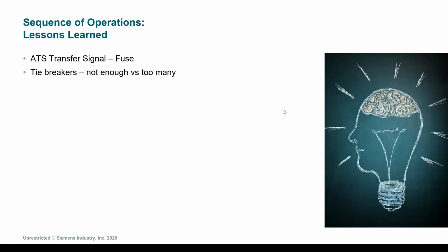Additionally, many of the parallel switchgear configurations have a different combination of too many versus not enough tiebreakers. Depending on how the system is intended to operate, there's the ability to have generator tie distribution generators. And this would allow the system to operate in an A or B bus configuration, but obviously has extended impact in terms of the actual physical space.